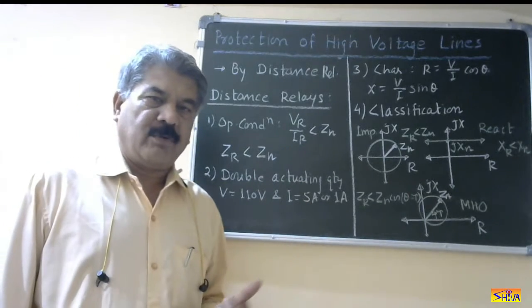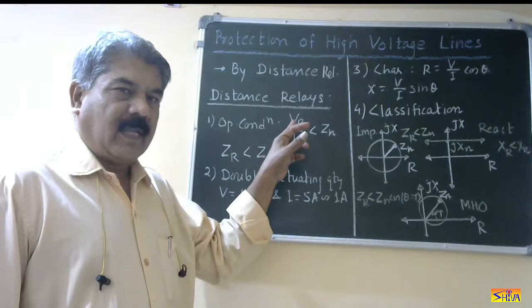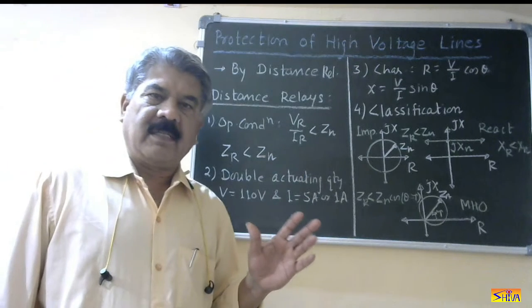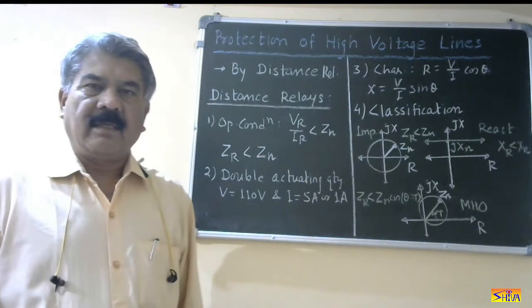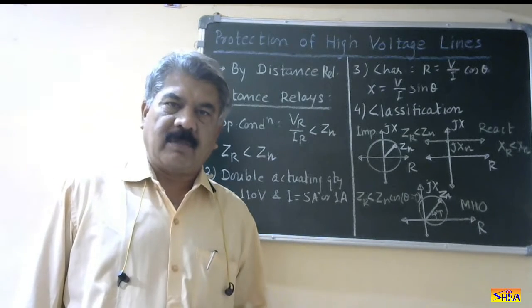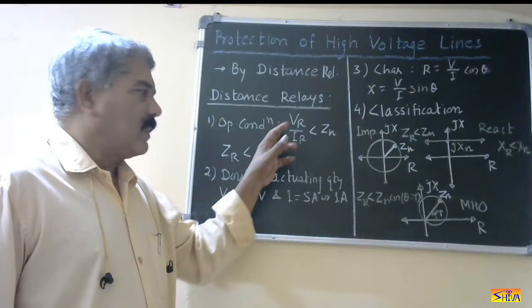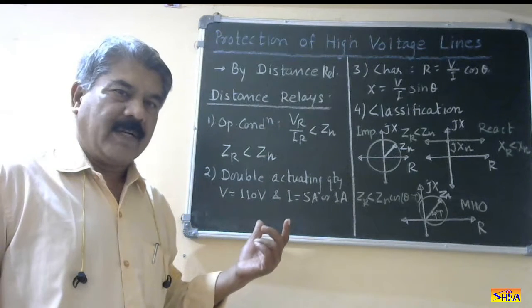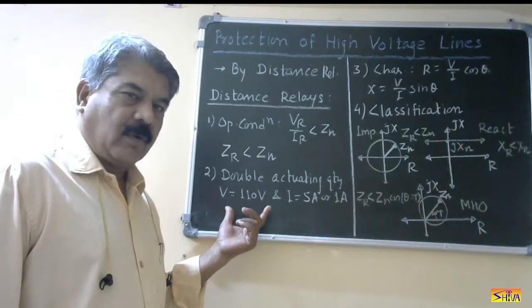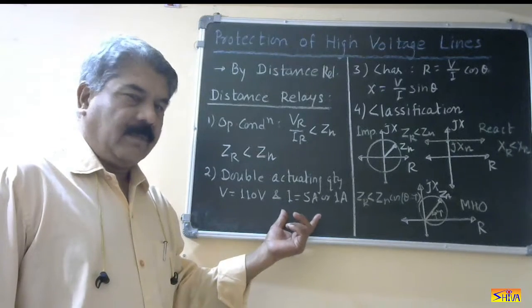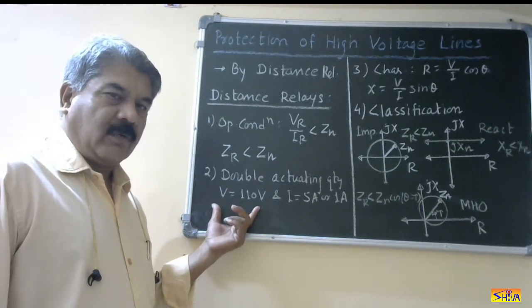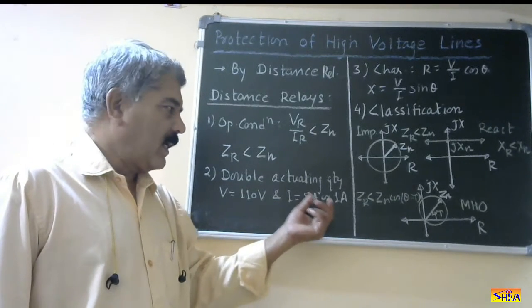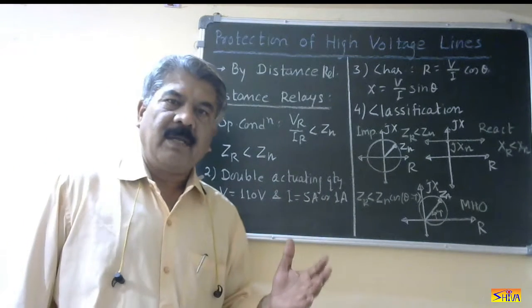The second point is about the actuating quantities. For operation of the distance relays, we require voltage as well as current. Therefore, this is a double actuating quantity relay, whereas an overcurrent relay is a single actuating quantity relay because there we measure only the current. Here we need to measure voltage as well as current. Therefore, if it is an electromagnetic relay, there will be two windings — one is a voltage coil or pressure coil, and the second is a current coil. The standard rating of the voltage coil is 110 volts, and the current coil can be either 5 ampere rated or 1 ampere rated.